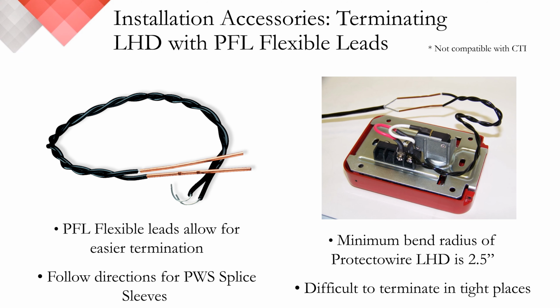It's possible to install pull stations in line with standard linear heat. However, due to its spring steel construction, Protectowire cannot be bent less than its allowable 2.5-inch bend radius without potential damage. Our PFL flexible leads allow the termination of Protectowire in these tight spaces without compromising the detector.